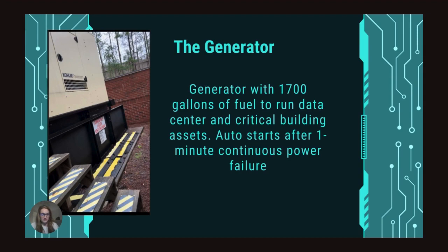The UPS only needs to handle 45 minutes because that's about the amount of time it would take to refuel the generator. If something were to occur, like a hurricane, and the generator is almost out of diesel, they would shut it down and the load would go to the UPS, giving enough time to get the generator refilled with diesel. There are 2 breakers that come out of the UPS with big cables that run to the transfer switch box outside and to the outside generator, so they're constantly talking to one another.